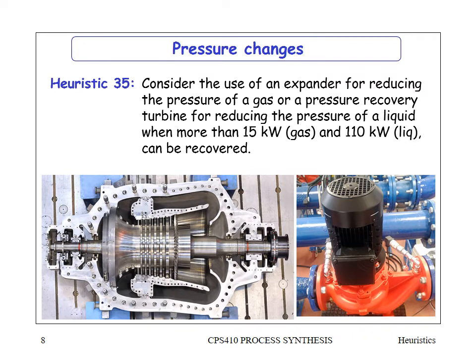Heuristic 35: consider using an expander for reducing the pressure of a gas, or a pressure recovery turbine for reducing the pressure of a liquid, when more than 15 kW is recoverable for gas or 110 kW for liquid. The illustration on the left is a gas expander to which a generator can be attached. If you can recover more than 15 kW from a gas being expanded, it becomes economically worthwhile. On the right is a liquid turbine: if you can recover 110 kW or more, it is worth installing a liquid turbine to recover that energy.